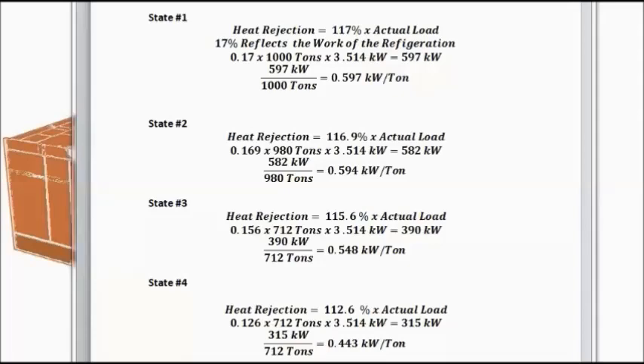In state 4, the chiller efficiency has improved quite significantly. And this time, the only change was in the condenser water temperature. As we put the temperature set point mode in automatic, and the condensed water temperature was reset from 85 degrees to 76 degrees, I would say that 0.443 kW per ton is a significant improvement over 0.548 kW per ton, primarily due just to condenser water reset.